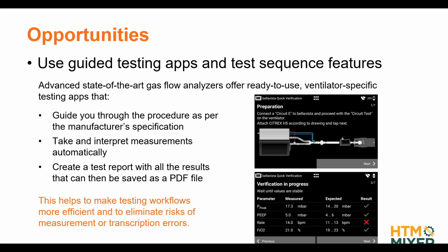So this helps, of course, to make testing workflows more efficient and also to eliminate the risk of reading errors, calculation errors, and also interpretation of these results. And additionally, because these applications are based on specific ventilators, we can also make sure that it loads automatically the correct settings for these ventilators. For example, the gas standard, gas type, and trigger settings. So it actually resolves all the challenges we have discussed in this session.